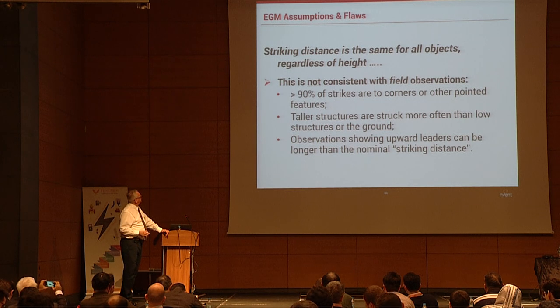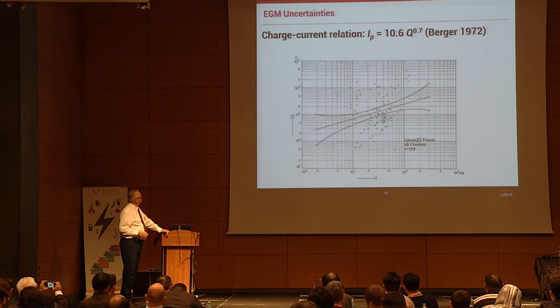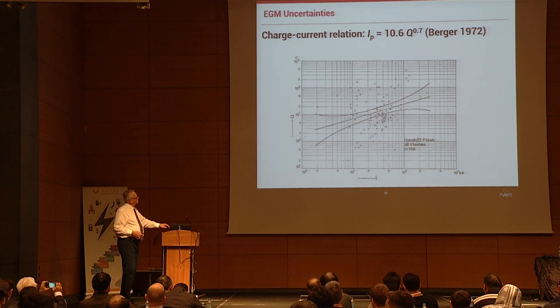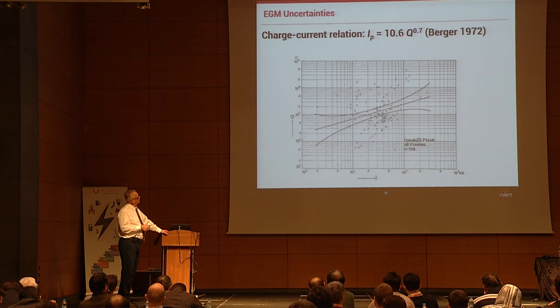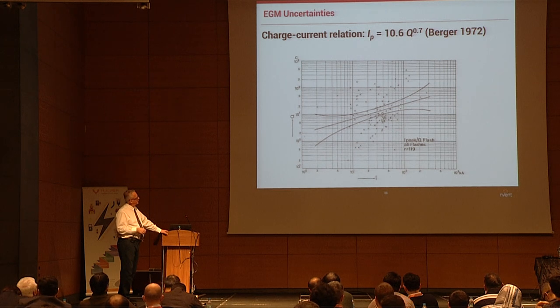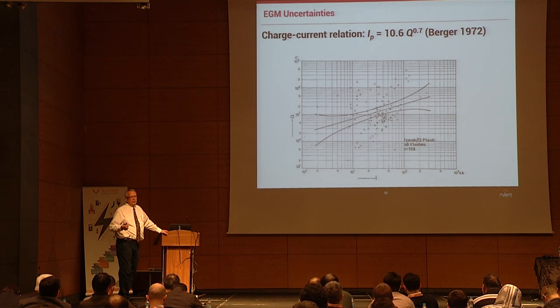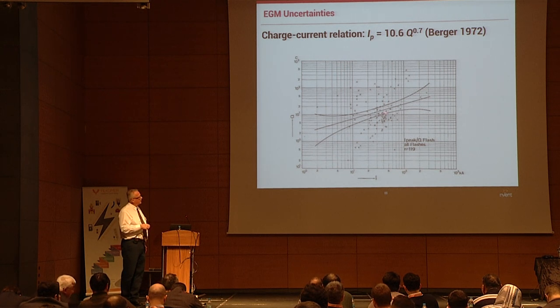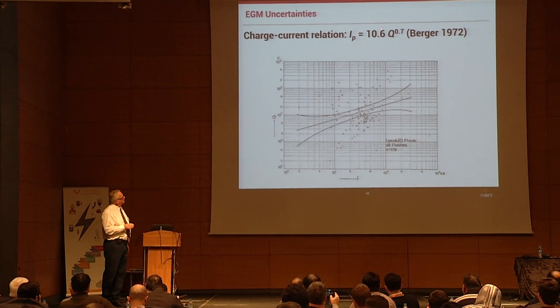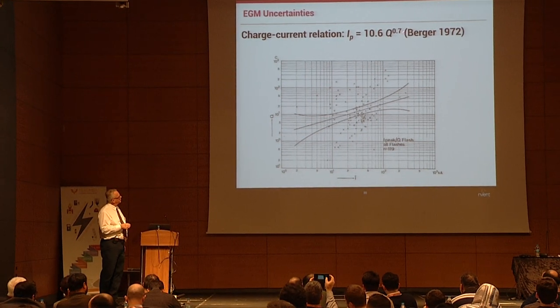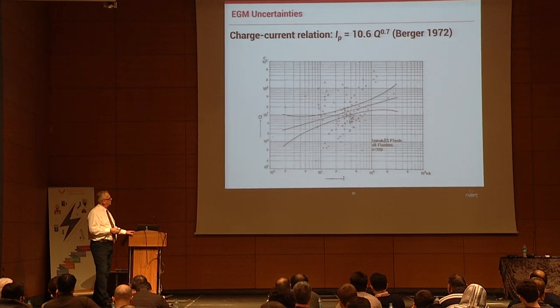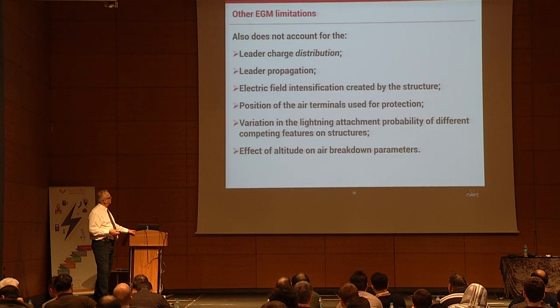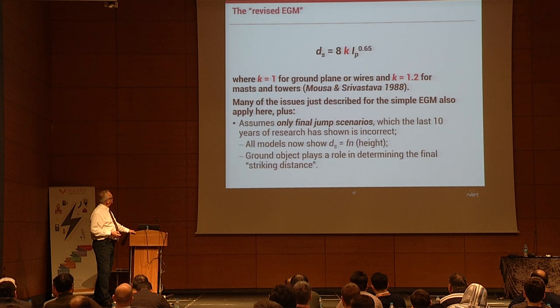The rolling sphere formula was actually derived from Professor Berger's test data. If a different professor were to fit the curve through those data points differently, the multiplier and root would change based on how the curve is fit — illustrating the limitations of this empirical formula.